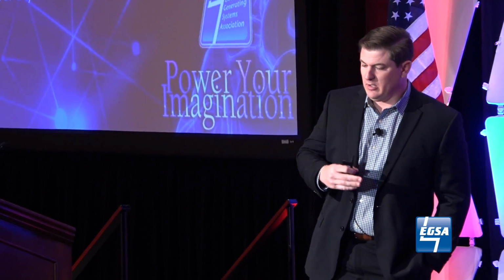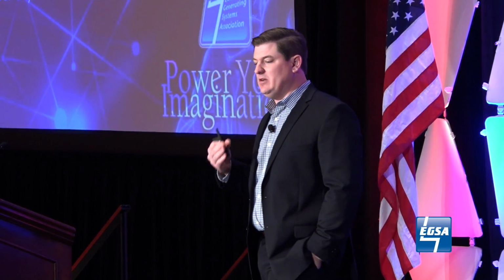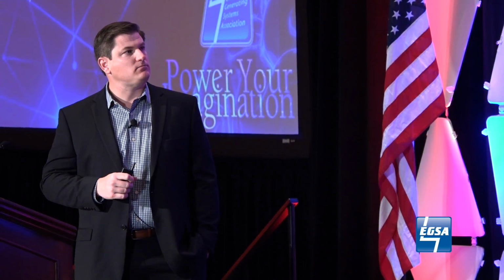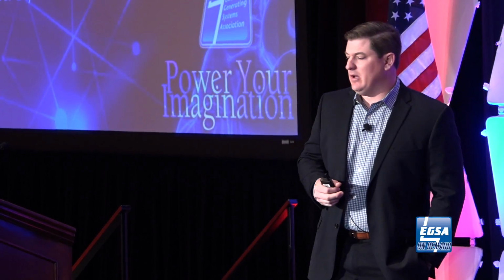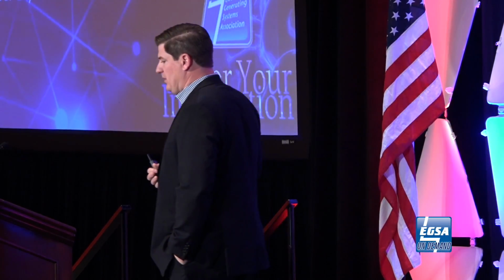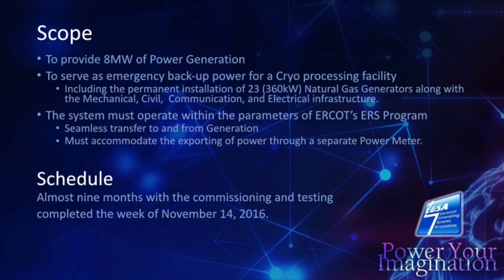We were also going to have a seamless transfer between utility and generation so that when we did participate in these emergency response events, we didn't lose power. And then we had to accommodate the exporting of power through a separate power meter. I know some folks peak shave and might have some arbitrage power that they send back. This is actually 8 megawatts bid into the real-time market around ERS activity.